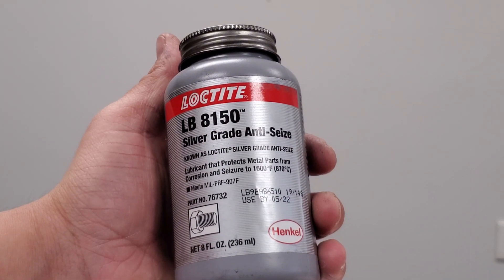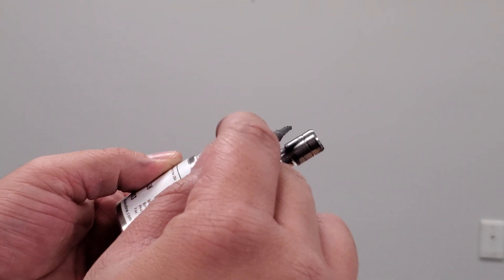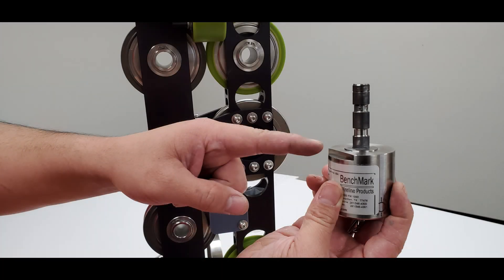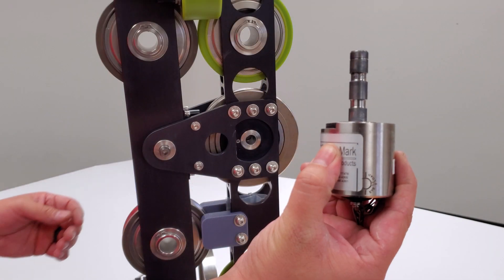Apply anti-seize compound to the shaft of the load pin. For proper installation, see that the flat part of the load pin matches up with the flat indentation in the frame body.